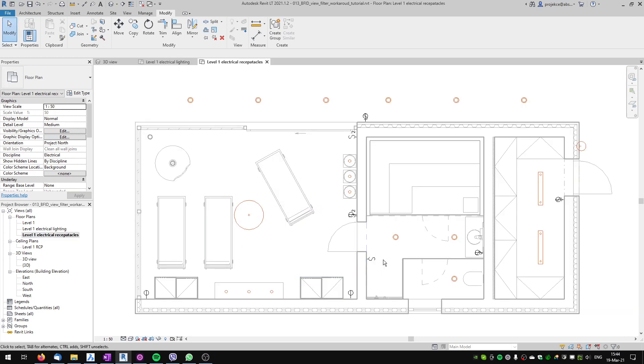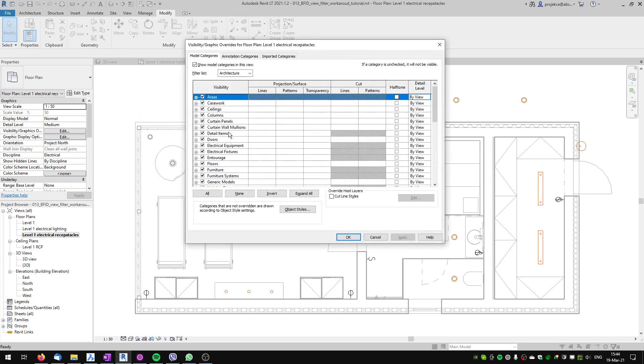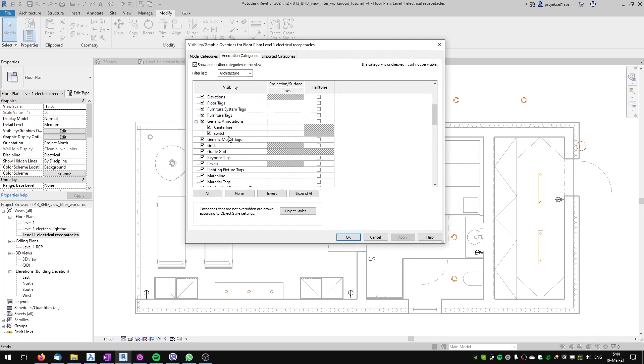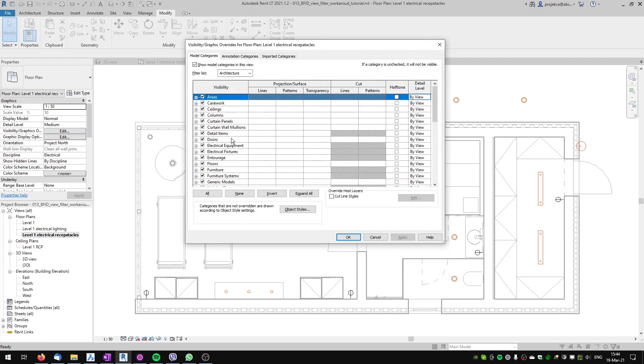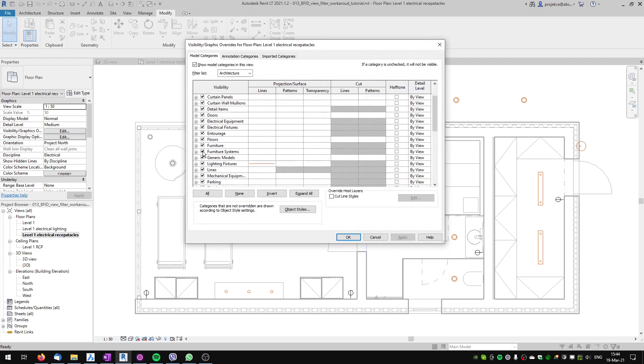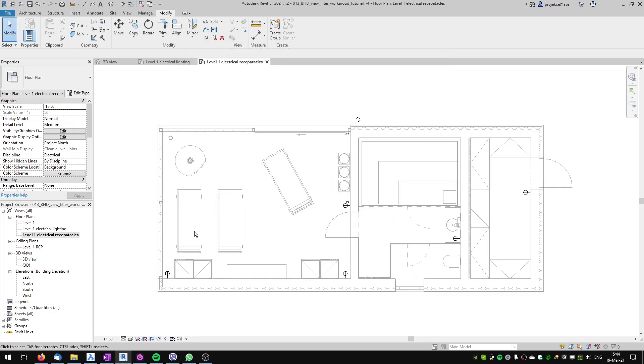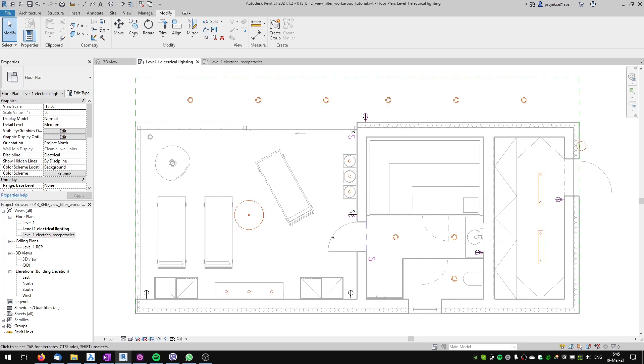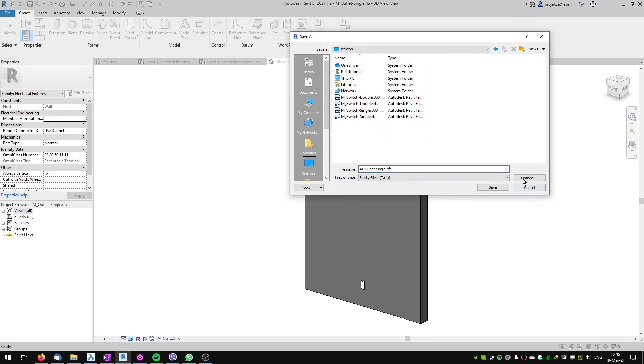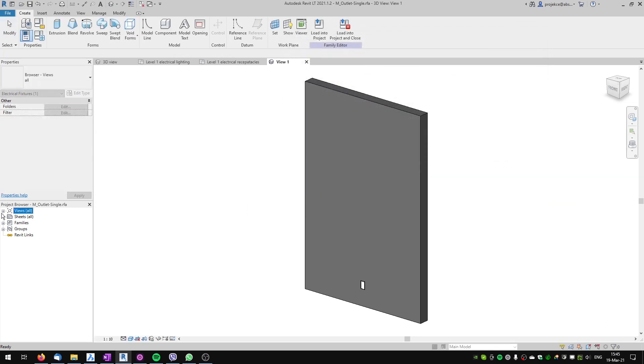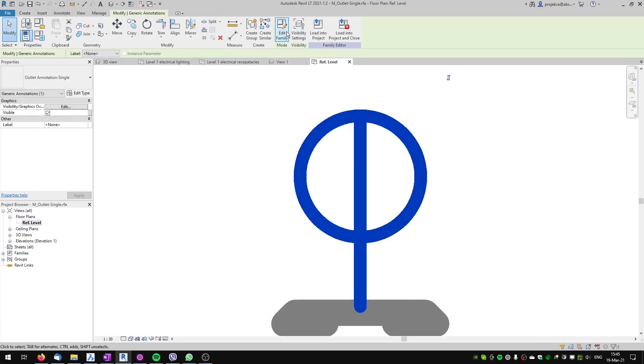All switch families are modified. I'll go to my electrical receptacles floor plan and hide the switch symbols by going to Visibility Overrides, annotation categories, generic annotations, and unticking the 'switch' subcategory. I'll also hide the lights by going to model categories, lighting fixtures, and unticking those. So in my receptacles floor plan only the receptacles are visible. But in my electrical lighting plan I can still see the receptacles, so I have to modify the receptacle families the same way as I did with the switches.